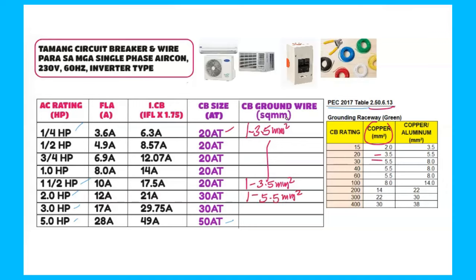So sa 30 ampere ang grounding niya is 5.5 mm square. The same with this. Okay, so sa 5 HP, meron tayong 50 ampere trip. So pasok siya sa yung 60 is 5.5. So we can use 8.0. Pwede siya natin i-upgrade. That is 8.0 mm square na ground wire. So ganun yung magiging grounding wire natin sa ating circuit breaker from the table 2.50.6.13 sa PEC.